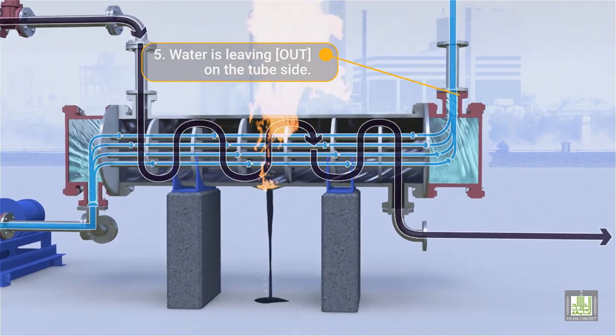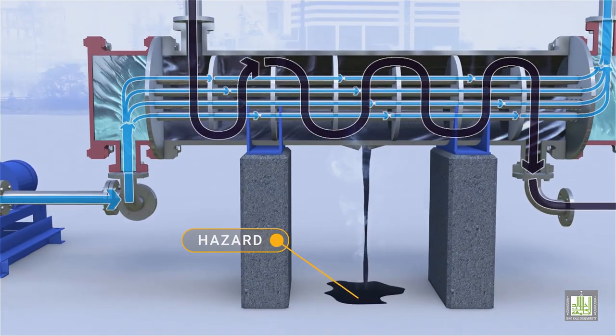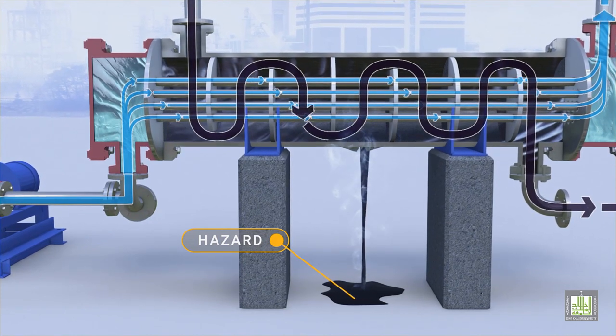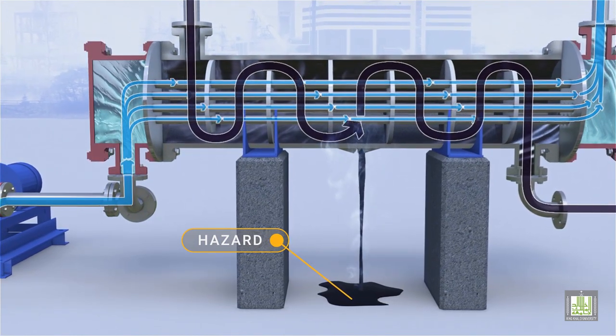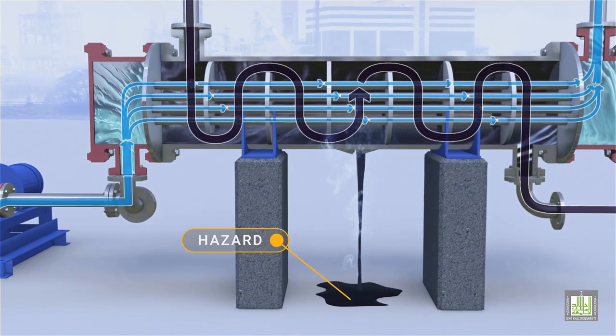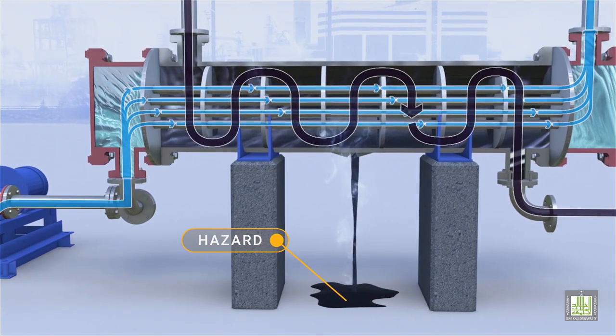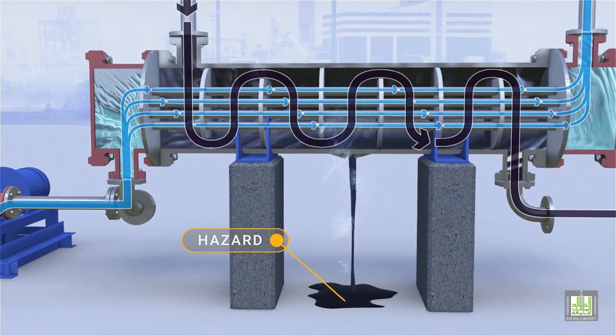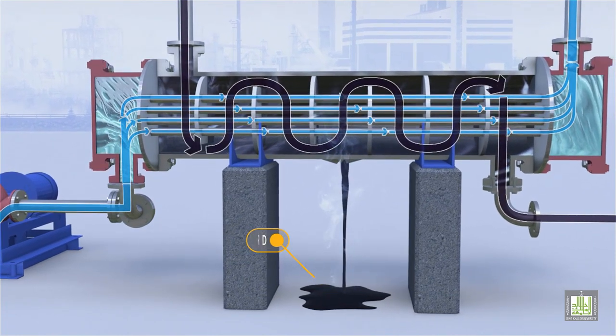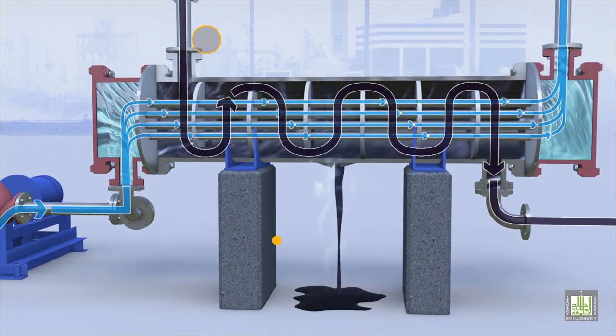The heat exchanger is typically provided with low or high point vents to remove water from tubes or the shell. Uncontrolled mixing of water with hydrocarbons can generate high-pressure conditions and can damage systems that are not equipped with pressure-relief devices.